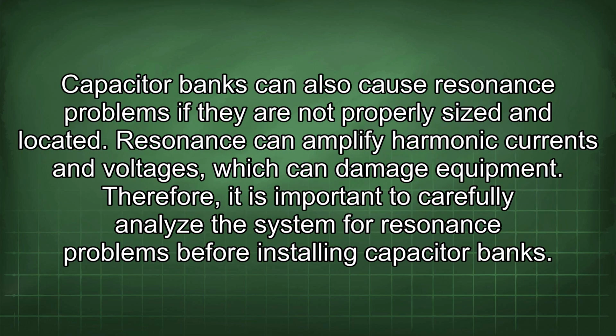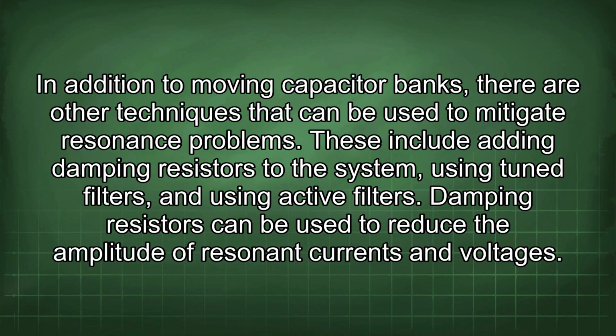Capacitor banks can also cause resonance problems if they are not properly sized and located. Resonance can amplify harmonic currents and voltages, which can damage equipment. Therefore, it is important to carefully analyze the system for resonance problems before installing capacitor banks. In addition to moving capacitor banks, there are other techniques that can be used to mitigate resonance problems. These include adding damping resistors to the system, using tuned filters, and using active filters.